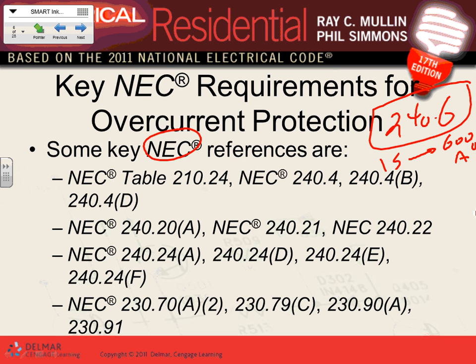So there's a few rules. Minimum circuit breaker for an apartment building is what? Service. We talked about this yesterday. 100 amps. How about non-dwelling? Minimum circuit breaker for non-dwelling, 60 amps. These are all from Article 230. So you guys are looking at them, the Article code.